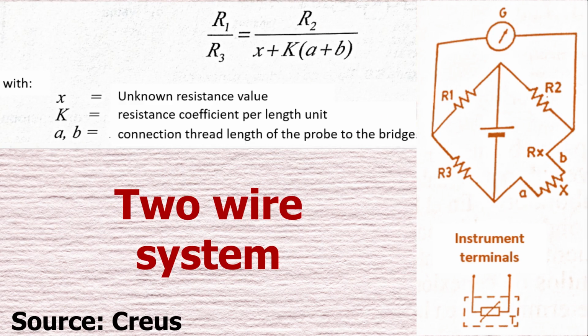The 2-wire assembly is the simplest, but it has the disadvantage that the resistance of the wires A and B connecting the probe to the bridge varies when the temperature changes, and this variation distorts the indication. Although these wires are of low resistance, the lengths that may exist in the field between the probe and the panel where the receiving instrument is add some resistance to the probe arm. Then the previous equation becomes this other one. The 2-wire systems are used with moderate connecting wire resistances, and when the reading does not need to be too accurate.